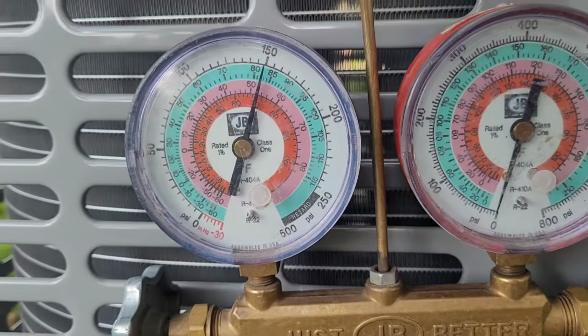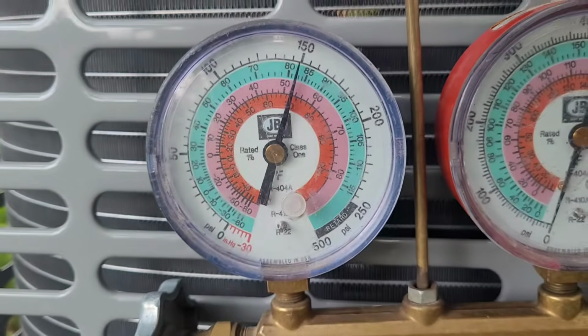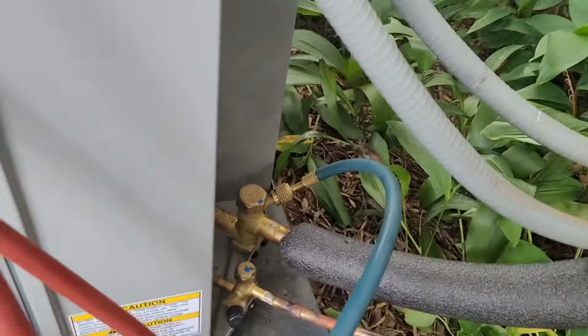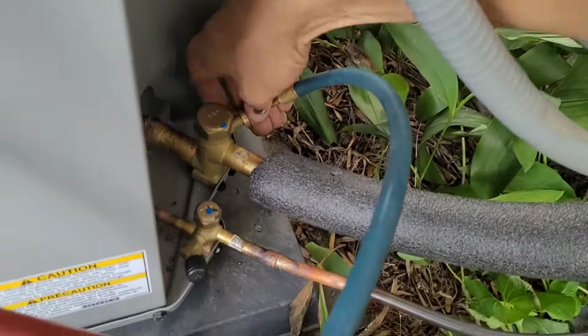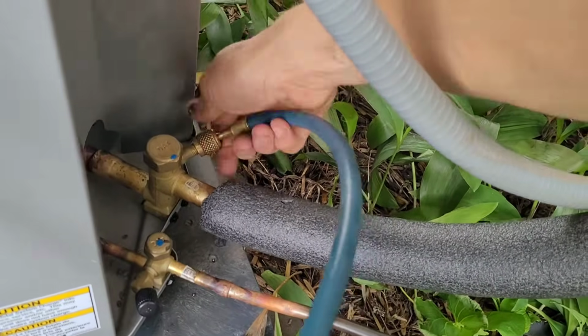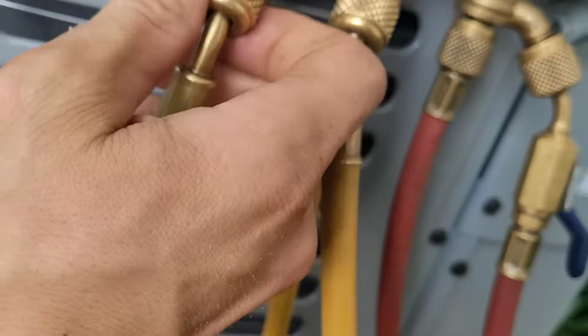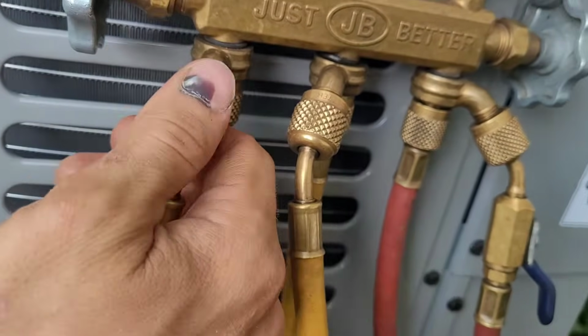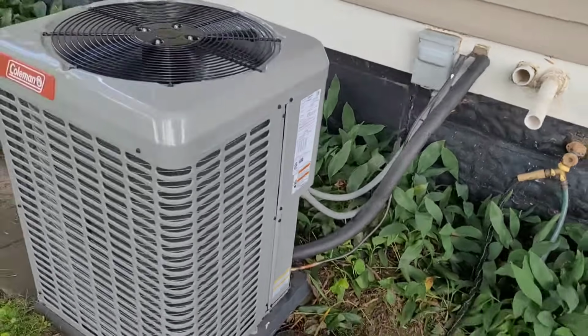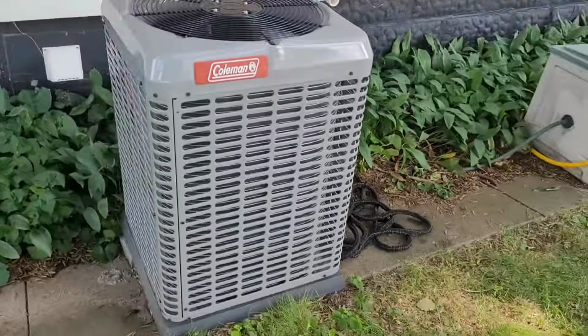So it's actually close to 85 degrees in the house, which is why our pressure is running so high. And this line set is actually short enough that the factory charge is adequate. These particular systems come with enough refrigerant for 15 feet of line set, so we're not going to add any refrigerant to the system. And there we are, all good to go. Happy Coleman unit.